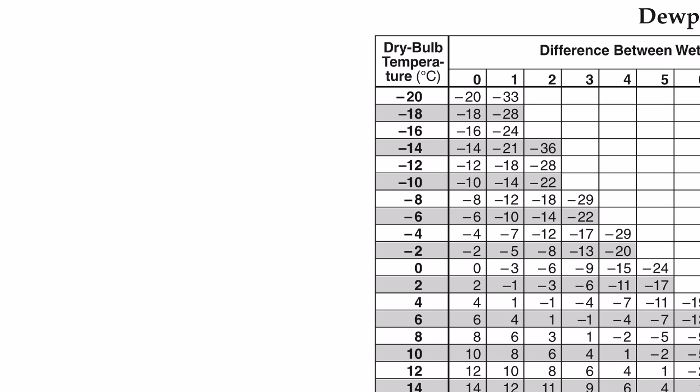you would be best off calculating the humidity or the dew point for the two numbers closest to the one you have, and then averaging them out. And so that's how we use our reference tables and a psychrometer to calculate humidity and dew point.